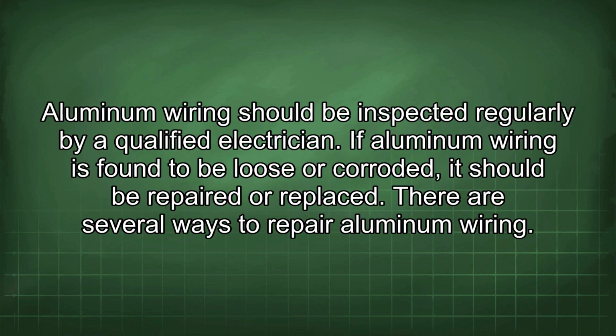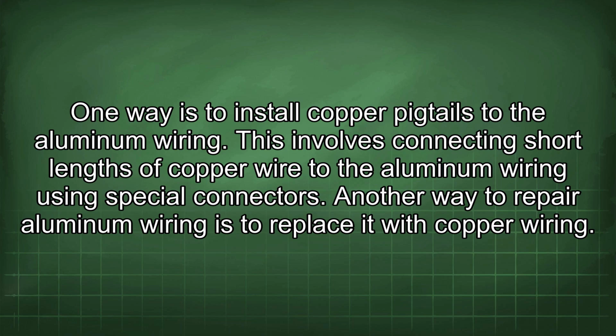Aluminum wiring should be inspected regularly by a qualified electrician. If aluminum wiring is found to be loose or corroded, it should be repaired or replaced. There are several ways to repair aluminum wiring. One way is to install copper pigtails to the aluminum wiring. This involves connecting short lengths of copper wire to the aluminum wiring using special connectors.